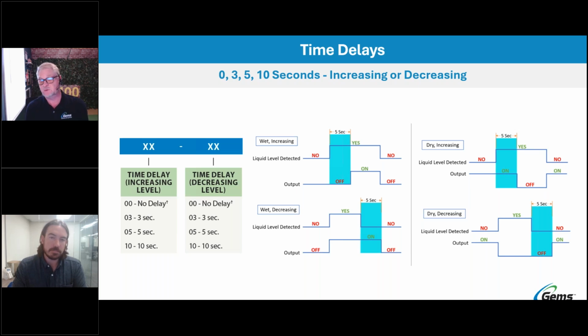The last option, if you so choose, is that you can add a time delay. The time delay is either on increasing, decreasing, or both. The purpose behind that is in mobile applications, you might have sloshing or turbulence, and you don't want too much of what they call chattering or false signals. So you want to build in a time delay. That time delay is between the time that the liquid is actually sensed, or the absence of liquid is sensed, and the signal output. So there's your built-in delay, kind of a built-in chill out period before it actually gives a signal.